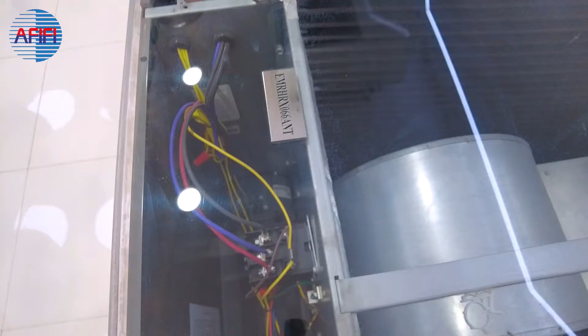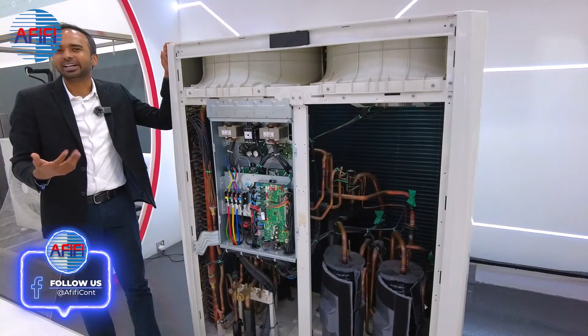Smaller than that, we have the mini VRF, which is a side discharge unit. It starts from around 10 kilowatts. You divide by 3.4, 3.51. For HP, you multiply by 0.8. The funny thing with VRF is that it's always rated in HP or kilowatts rather than tons, so that's why we convert. The smallest one is 25 kilowatts or 7 point something tons.